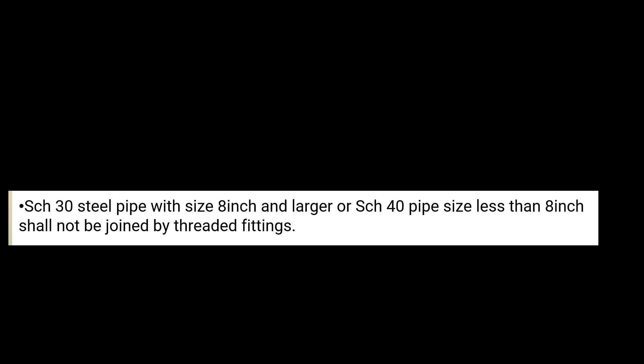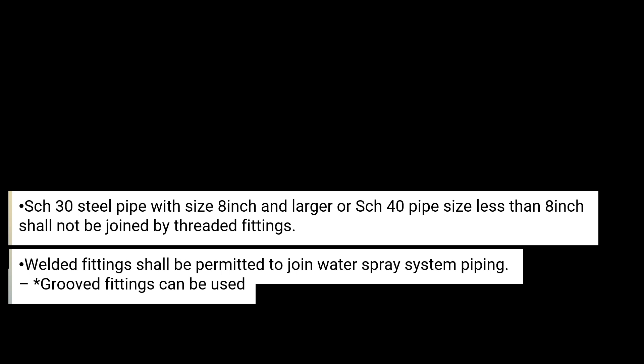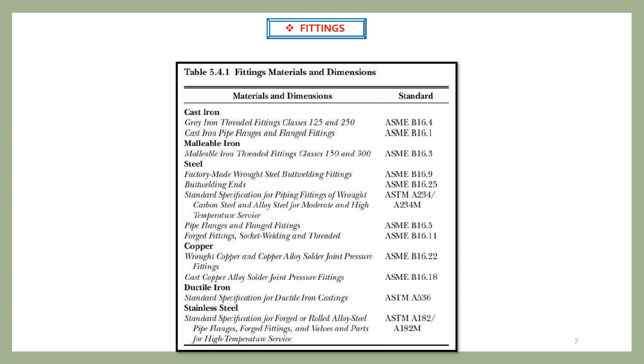This is the most important point to remember. Welded fittings shall be permitted to join water spray system piping, and grooved fittings can also be used. However, in most cases, since the water spray system is a dry pipe system, we are going to consider welded fittings only. The types of fittings which can be used are detailed in NFPA 15 table 5.4.1.